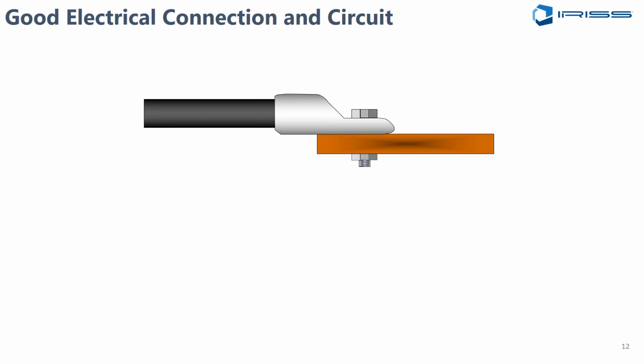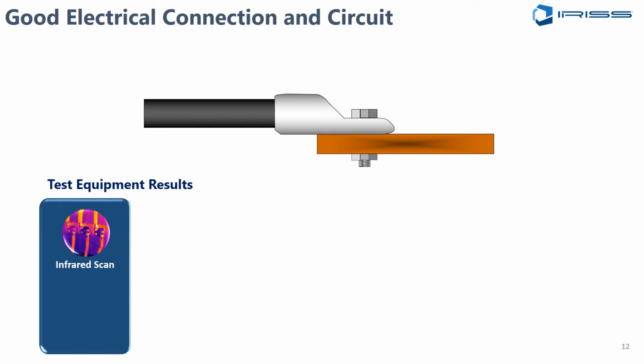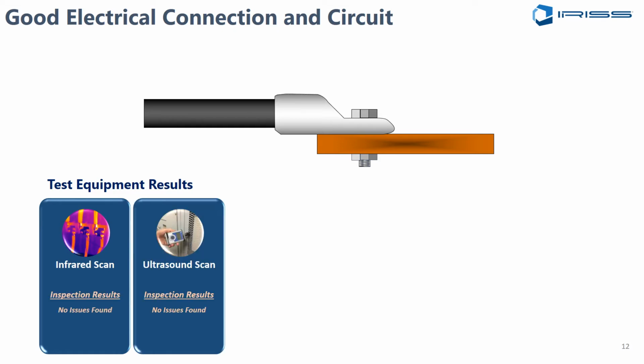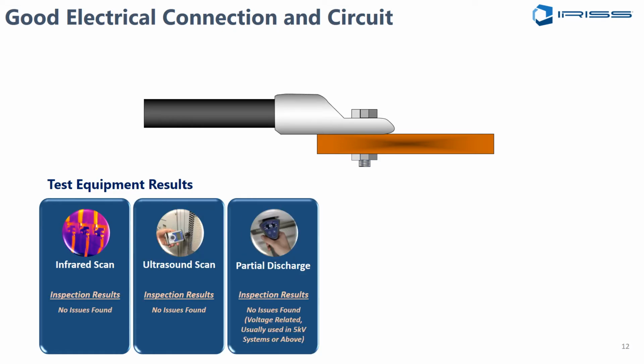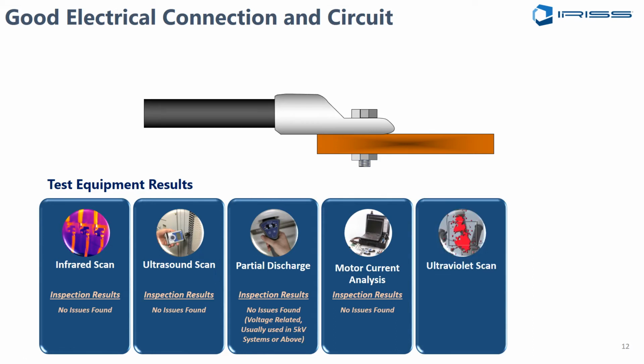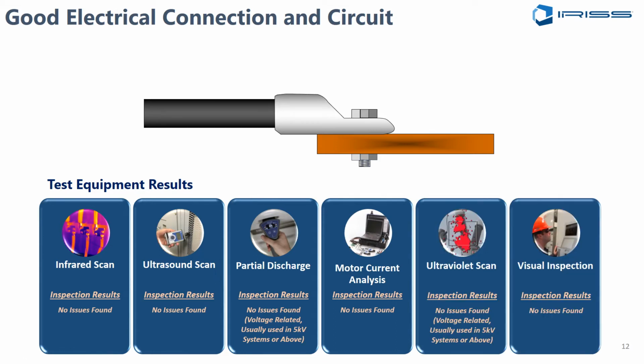Now, if we look at this circuit, I'm going to do this through condition monitoring. So the infrared shows 0, ultrasound shows 0, PD shows 0, motor current analysis shows 0, ultraviolet shows 0, and there are no issues with the visual inspection. I've done all of these tests and there is nothing wrong with the connection. That really means to me there's nothing physically I can do from a maintenance intervention standpoint to make this connection any better. I've proven to you by looking at this connection that there's nothing wrong with it. So we just move on.